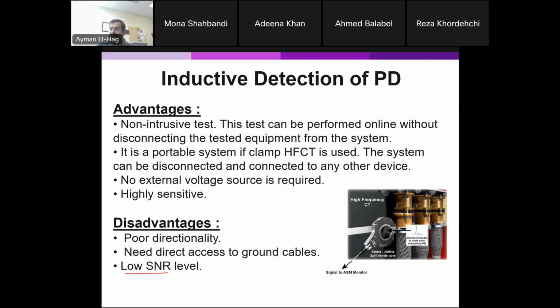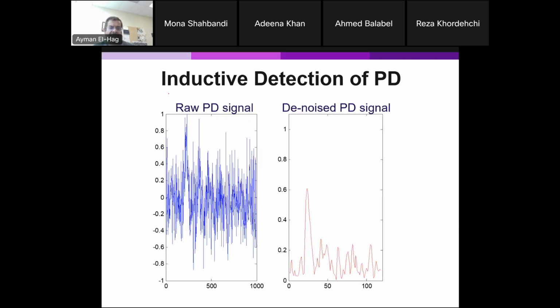What does this mean? It means that this is inductive, okay, so it would detect a lot of noise with it as well. When something has a low signal to noise ratio, it means that the signal will be highly corrupted with noise. And let's have an example. This is an example of a partial discharge that we measured here at the high voltage lab. So when you look at that signal here, basically, you don't know if that is actually a signal or if it is actually noise, okay? Unless you do some denoising techniques, and this is what happened here, and you can see clearly the pulses coming out of it. So that is clearly a partial discharge.